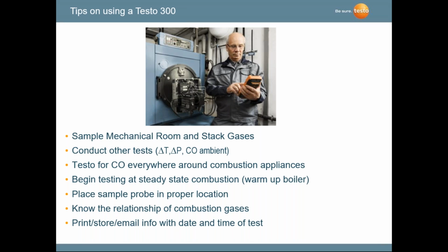You have the capability of conducting other tests. You can do delta T, delta P, carbon monoxide ambient. I showed you the draft and the CO ambient measurements that we do. You can check carbon monoxide everywhere around the combustion appliances.